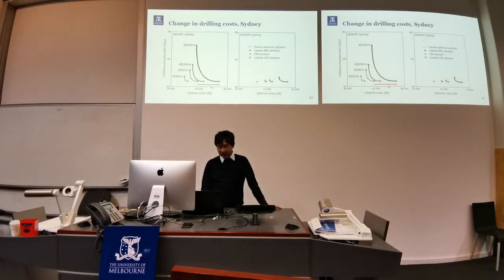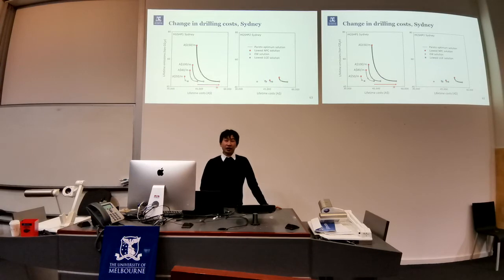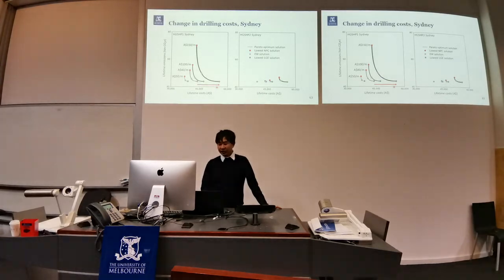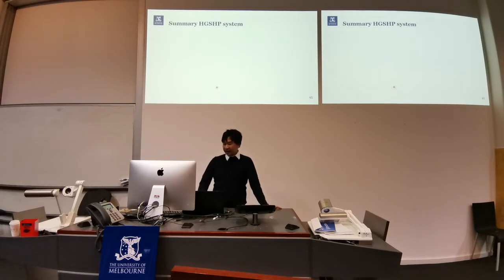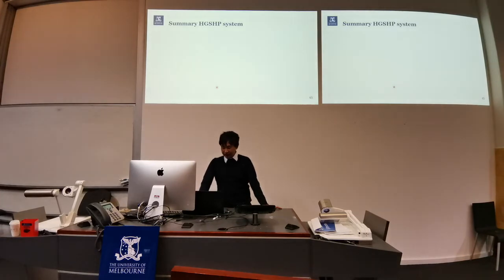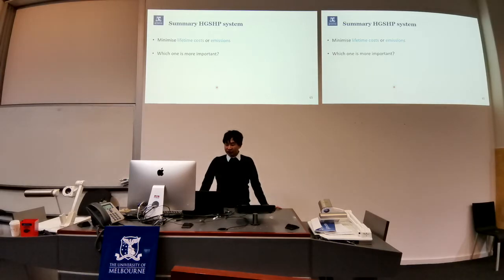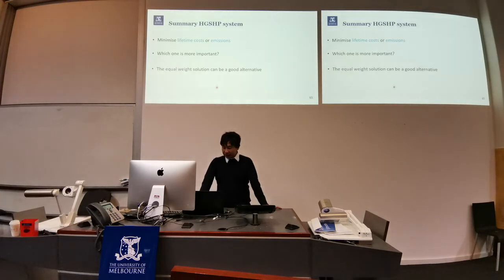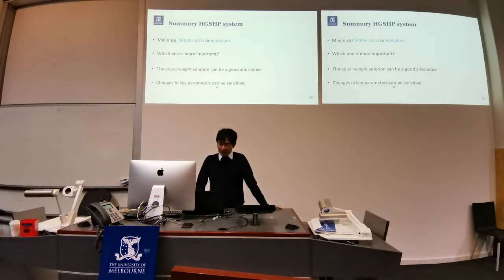The lowest emission factor is practically unchanged between this drilling cost and the earlier one, as they effectively represent the ground source heat pump system. In summary, a hybrid system can be designed to either minimize the lifetime cost or emission, but those solutions are not the same. All stakeholders may consider the weighted importance of each factor. The equal weight solution can be a good alternative, and changes in key parameters will impact the hybrid system feasibility, so they need to be considered properly.